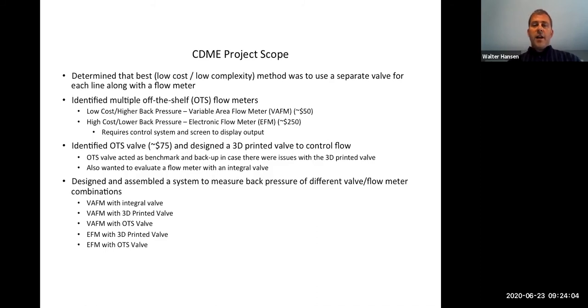So we identified multiple off-the-shelf flow meters. The simplest, cheapest design is the mechanical variable area flow meter. This is the kind you might have seen on compressed gas cylinders—it has a ball that floats inside a clear plastic housing, simple design. But we were concerned that the variable area flow meter might present too much of a restriction and create too big a pressure drop between the ventilator and the patient.